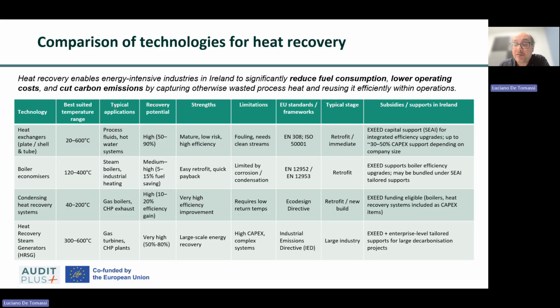Boiler economizers recover heat from boiler flue gases, typically operating in the temperature range of 120 degrees Celsius to over 400 degrees Celsius. They are widely used in steam generation systems across industrial facilities, hospitals, and commercial buildings. Economizers generally deliver fuel savings of between 5 to 15% by preheating boiler feed water. They are attractive because they are relatively inexpensive, straightforward to retrofit, and often provide short payback periods. Their effectiveness is limited by flue gas temperatures and the potential for corrosion if temperatures fall too low. Economizers are a mature technology and are eligible for support under SEAI business energy efficiency programs.